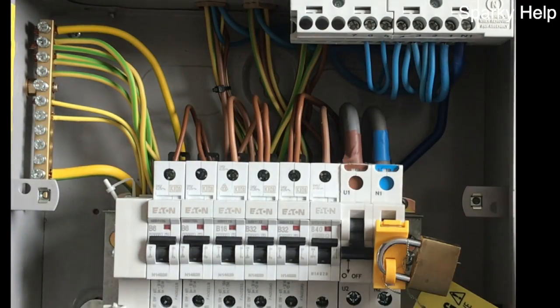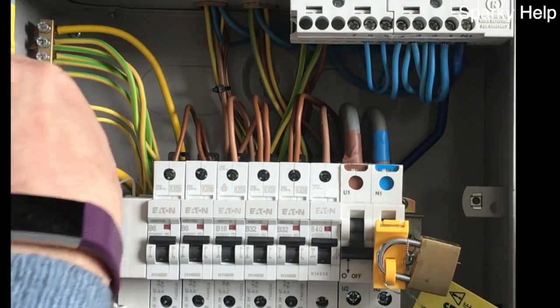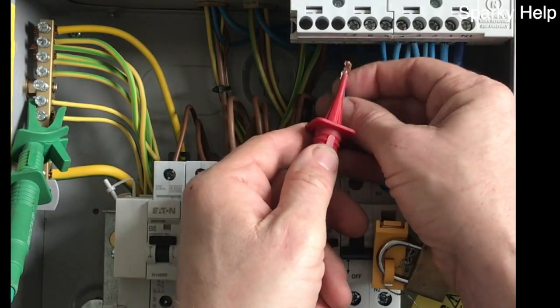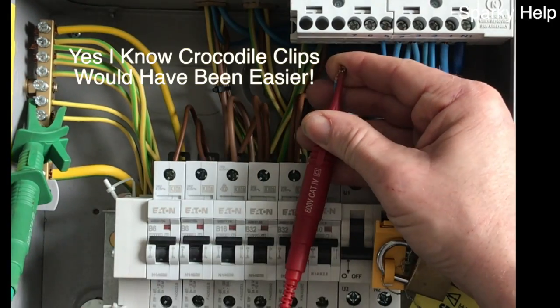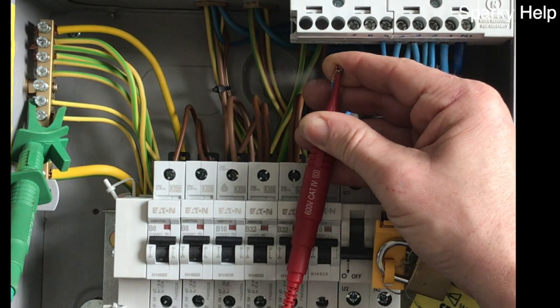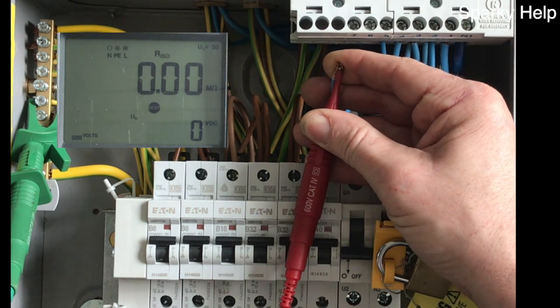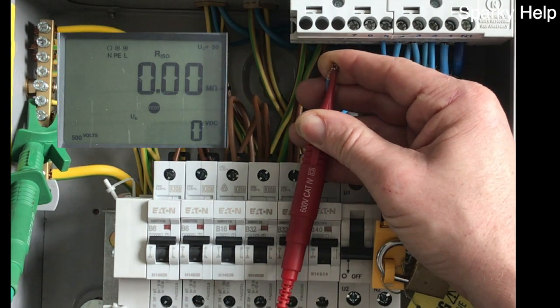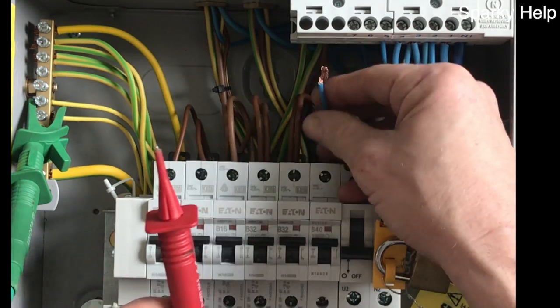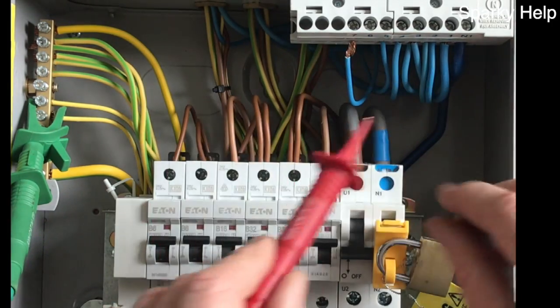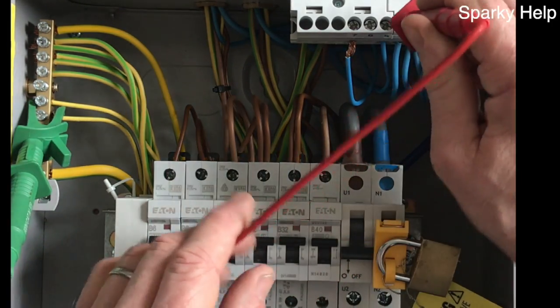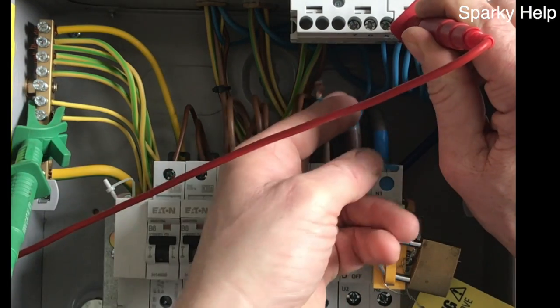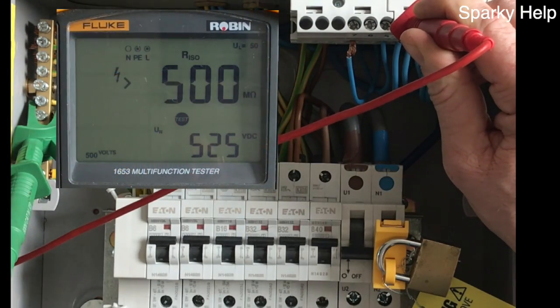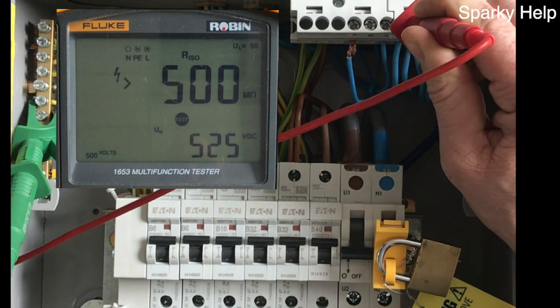Again, I'll start with number 6. And as luck would have it, that would give us a 0 on that particular one, but we can just check, make sure. I'll test all the others in place, so I don't need to do that one. So leave that one out, test all the others to earth, and they've all come greater than 500, so that's good.